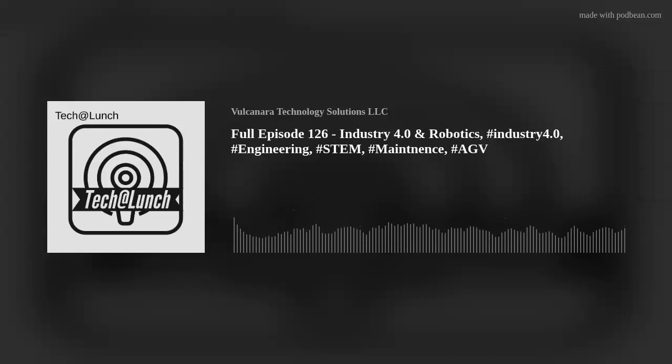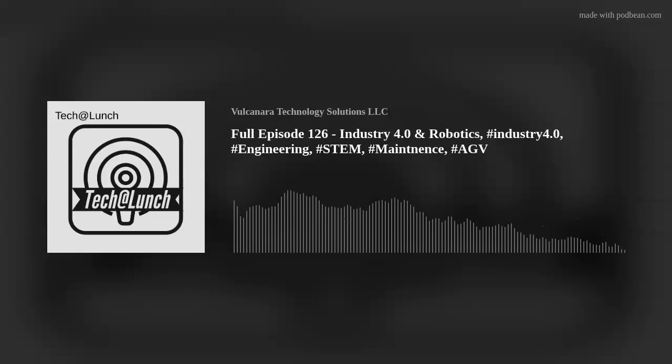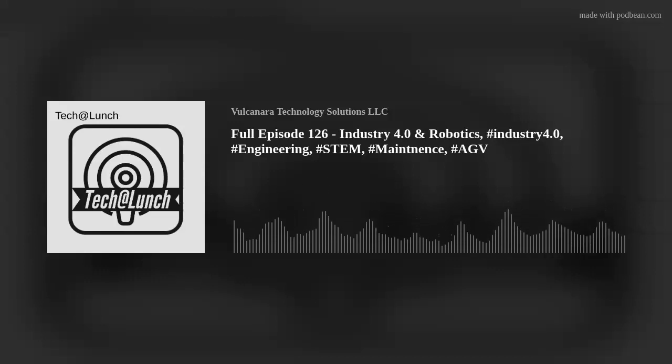And two of the best systems for that type of analysis, which give the administrator and the technician, if they're experienced enough, a lot of high-level growth and vision, is digging into the ELK stack, into Kibana and stuff like that, because it saves your MQTT messages as flat files. Meaning now you can go back and break down every little topic thread of every single message. So now you can start seeing, okay, like you said, your nuisance fault: did it just recently change to a nuisance fault? Did I go from a warning to an error? Or did I go from an error to a message?